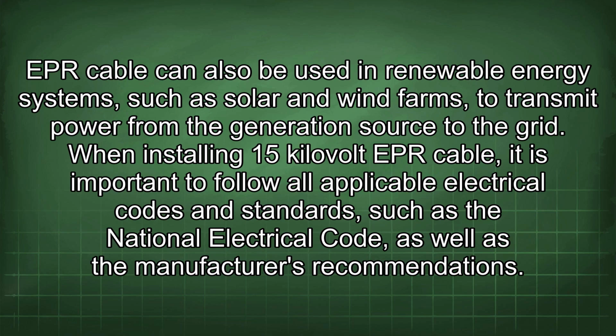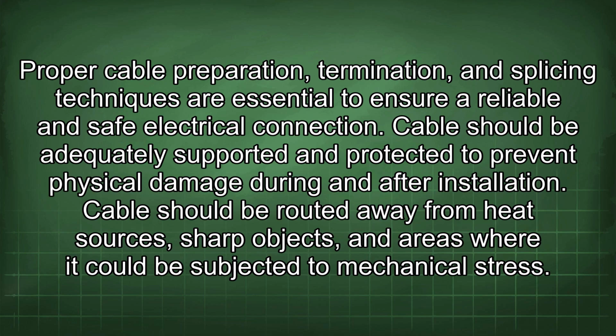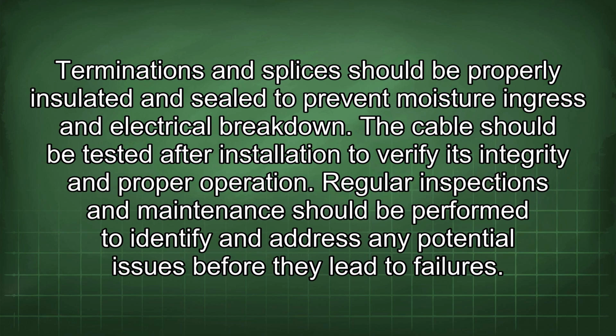When installing 15 kV EPR cable, it is important to follow all applicable electrical codes and standards such as the National Electrical Code, as well as the manufacturer's recommendations. Proper cable preparation, termination, and splicing techniques are essential to ensure reliable and safe electrical connection. Cable should be adequately supported and protected to prevent physical damage during and after installation. Cable should be routed away from heat sources, sharp objects, and areas where it could be subjected to mechanical stress. Terminations and splices should be properly insulated and sealed to prevent moisture ingress and electrical breakdown. The cable should be tested after installation to verify its integrity and proper operation.